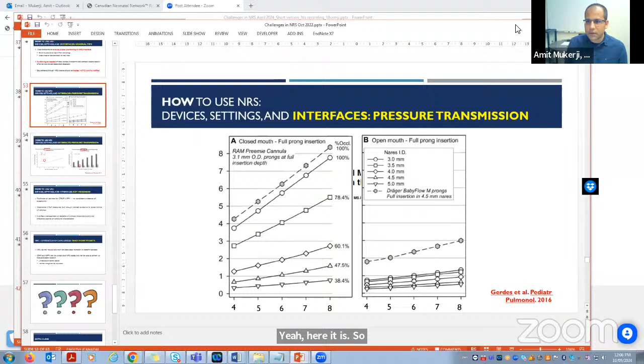Here are some data on the RAM cannula pressure transmission compared to a Draeger full interface. I'm just going to orient everybody to what this slide means. Most of our babies have their mouths open, so we can look at panel B, where the mouth is open. The x-axis shows the set pressure, so as a user, you set a certain amount of pressure, and the y-axis shows what the measured pressure is. The gray dots represent the Draeger Babyflow prongs, which are the more traditional kind of nasal prongs that I've shown you. You can see that the pressure transmission is much greater with that kind of interface compared to the RAM cannula, where with an open mouth there is significantly more loss of pressure.